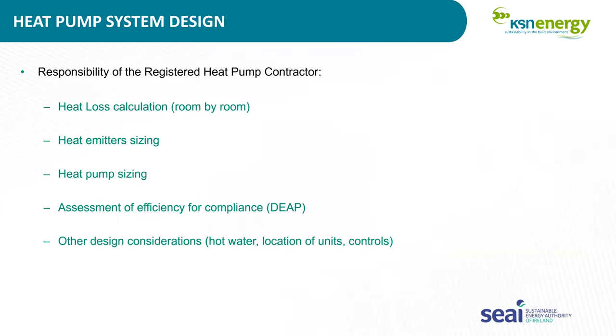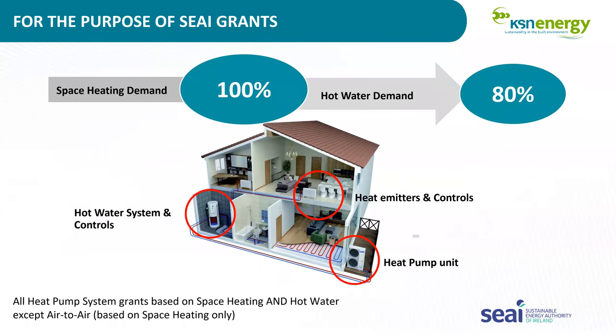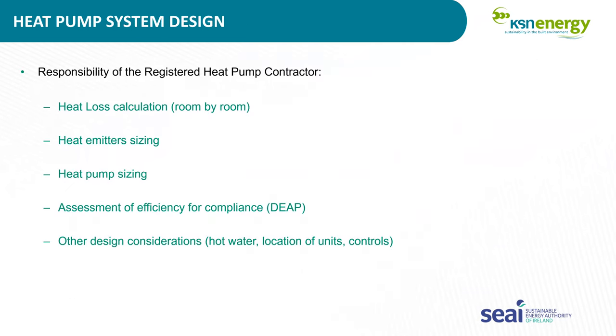The next thing, what's the responsibility of the register or the design? Who's responsible for it? So the heat pump contractor, they have to take responsibility of the design of the system. Sorry, I'll just flick back there. When we say the system as well, it's not just the unit. It's not just a case of coming in and putting the heat pump in. They must look at the hot water system. They must look at the control of the hot water. They need to look at the heat emitters, whether it's underfloor heating, radiators, fan coil units, whatever sort of heat emitters are doing it, and what control is on it. So all of that is encompassed on the heat pump contractor, the registered contractor.